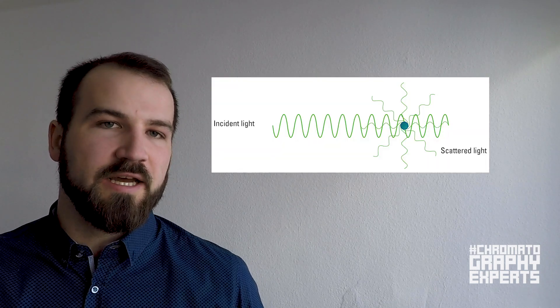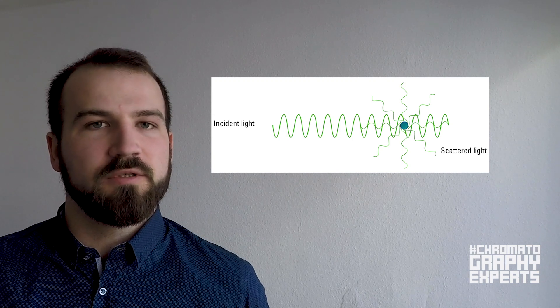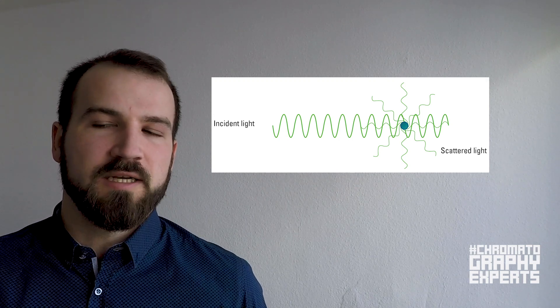In light scattering we have one laser that points directly on the flow cell, and then around the flow cell we have our detectors positioned at different angles to see the scattered light that is scattered by the sample flowing through the flow cell at different angles. From the position of these angles we can do various calculations about the molecules that flow through the flow cell.